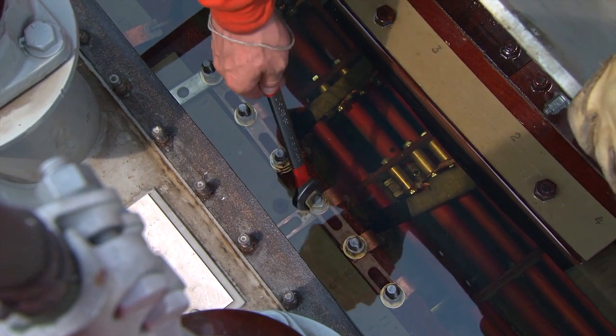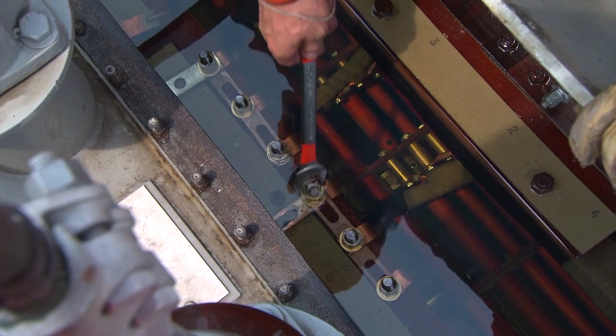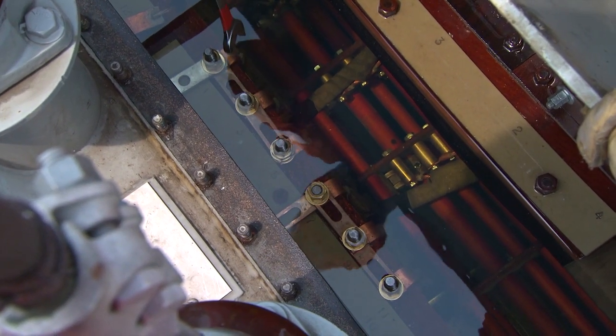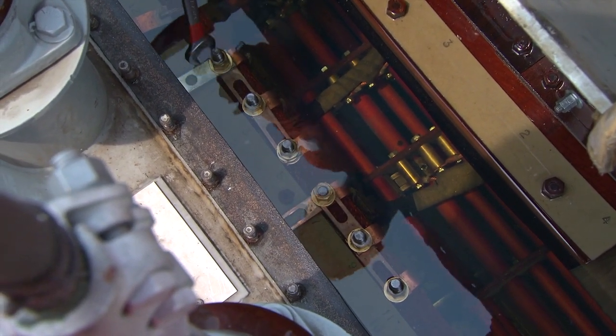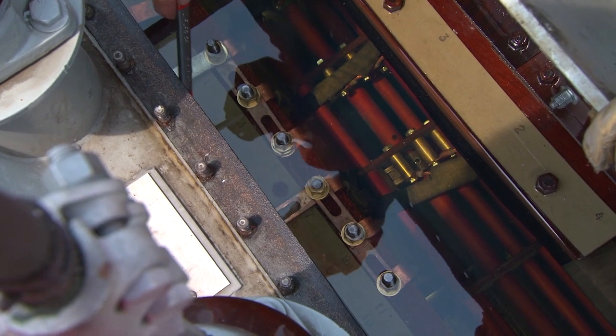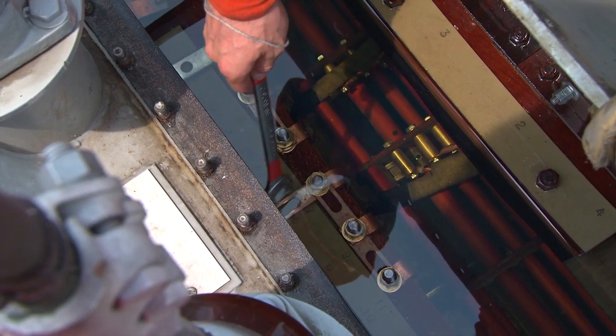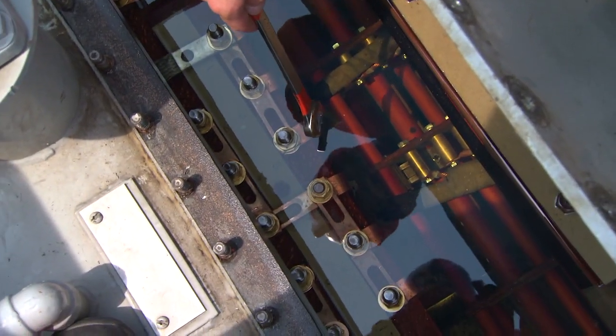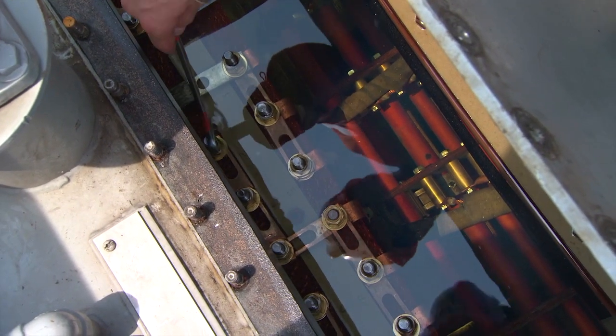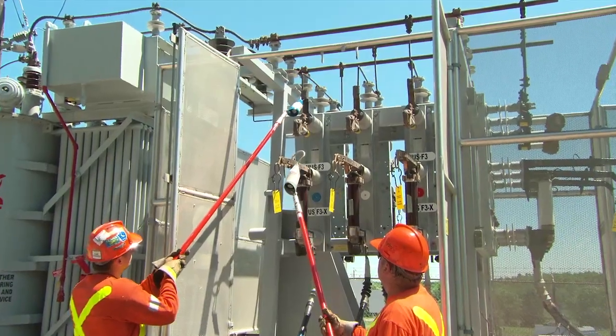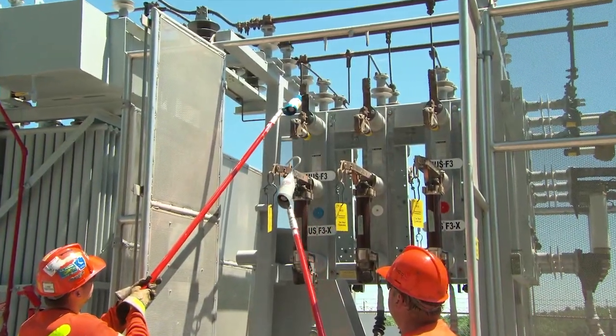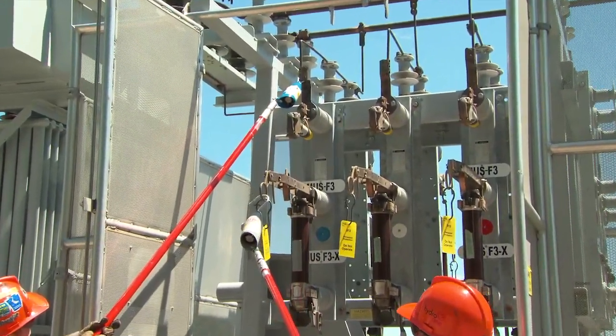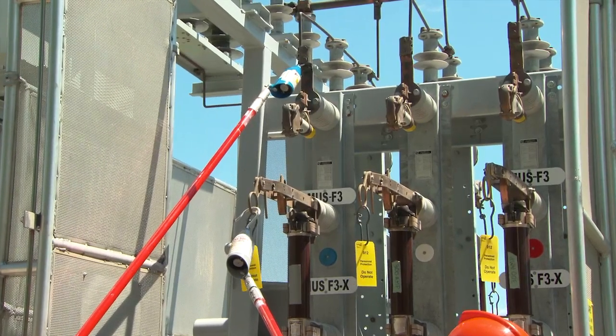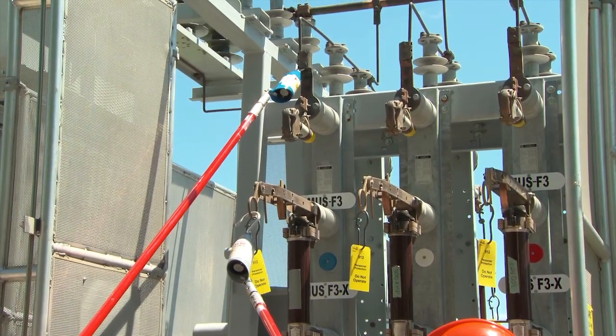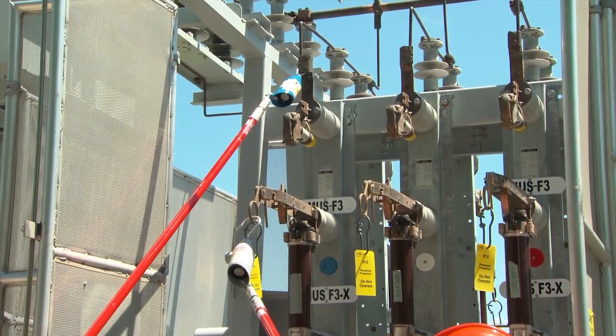Mobiles that are not equipped with a ULTC, like this particular unit, must be taken off potential in order to readjust the voltage if necessary. This is why it is important to perform all necessary calculations and ratio testing when selecting your tap positions prior to switching. Perform feeder phase checks on all 3 phases. If the phasing is incorrect, it will have to be adjusted with the MUS off potential.